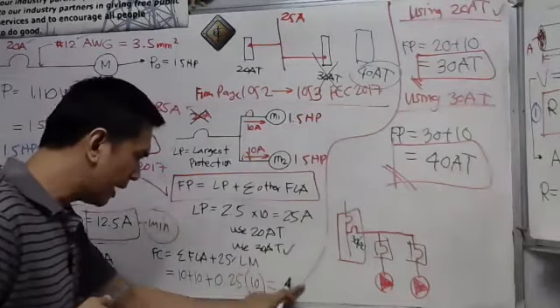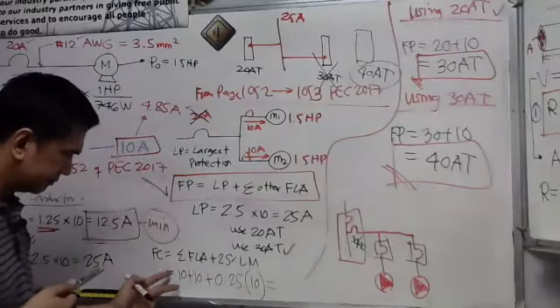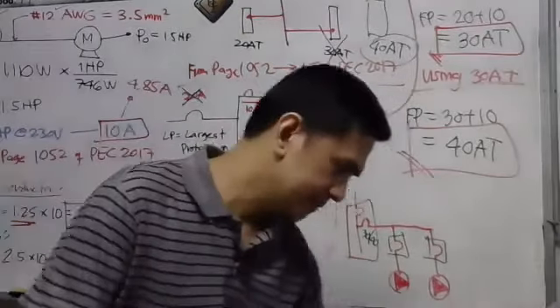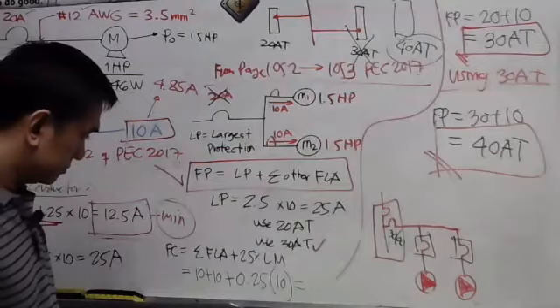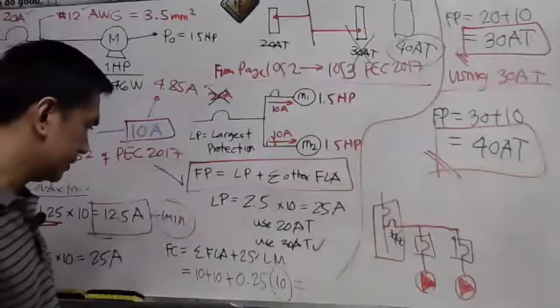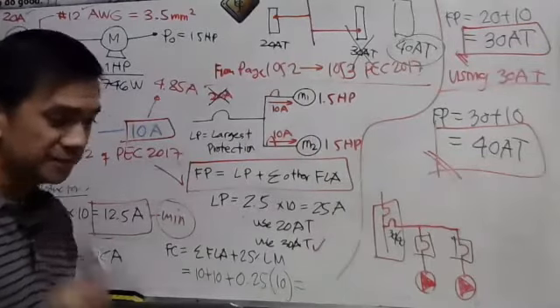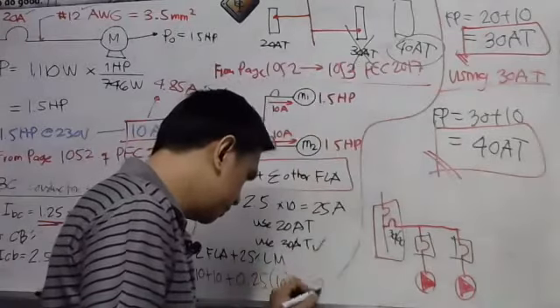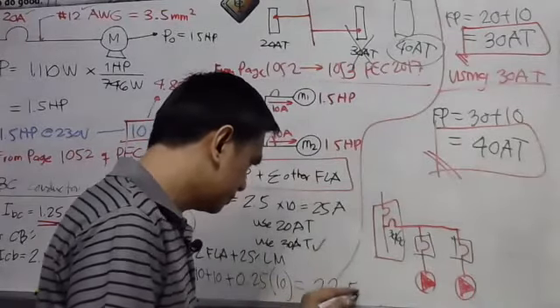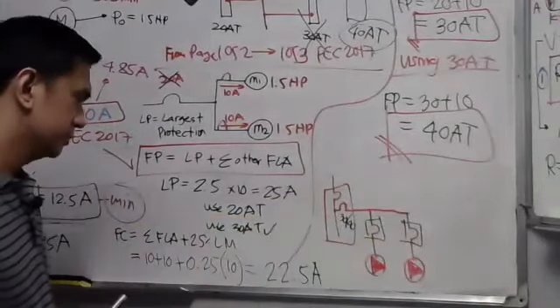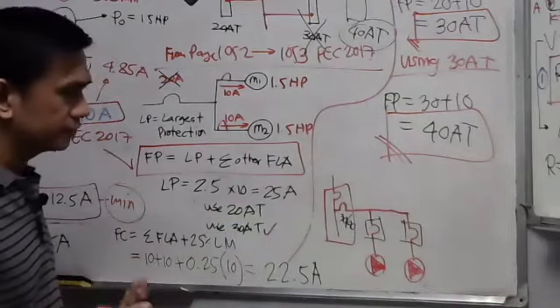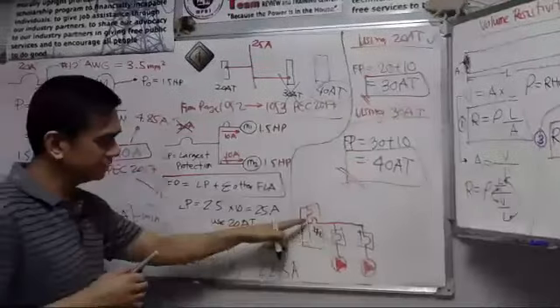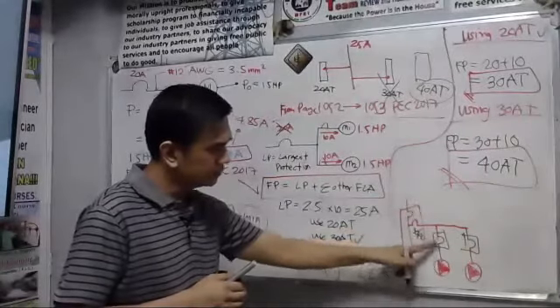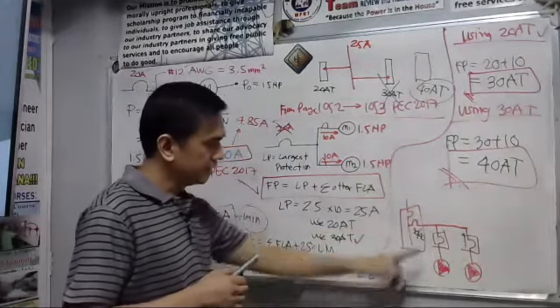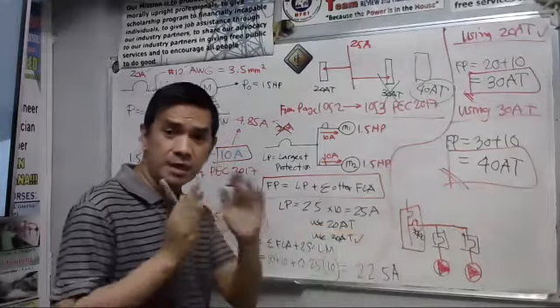So what will be the minimum ampacity of the feeder wire here? So how much is this? This is the minimum size of wire. So that is 20 plus 2.5, 22.5. That's the minimum size ampacity of the wire you're going to use. 22.5 amperes. Minimum size, you can use 3.5 square millimeter here, no? Well, it's better you use the next larger size, 5.5, and the 3.5 you use here for the individual motor. Okay, so the 3.5, 3.5, and in here 5.5. That's a better electrical design.